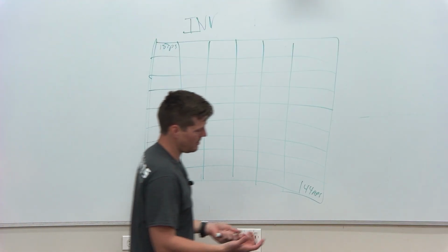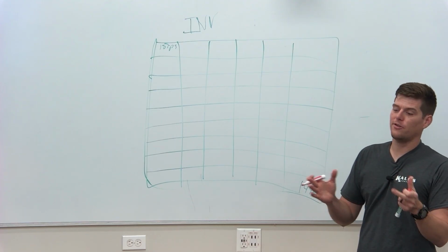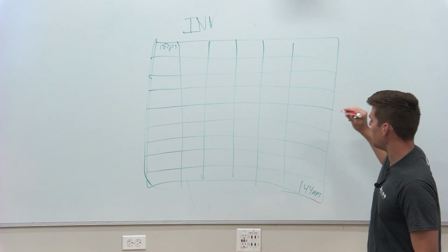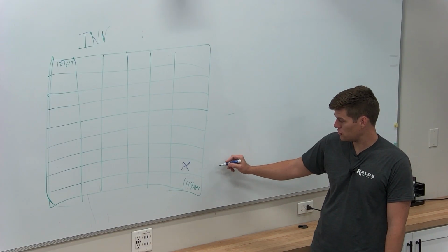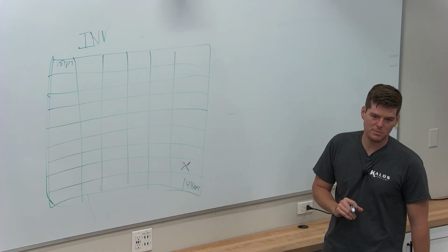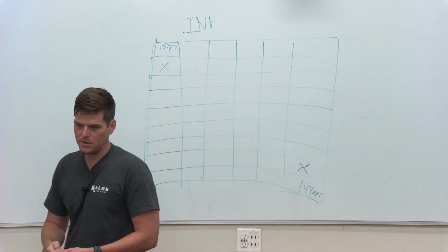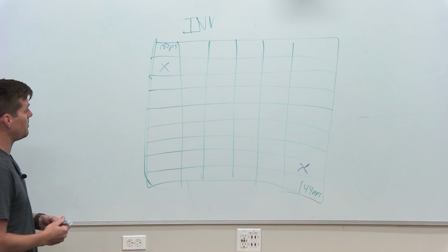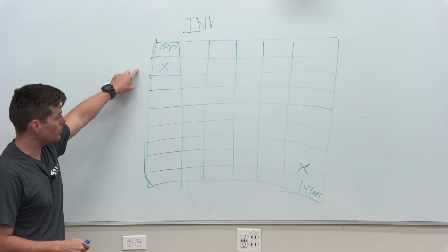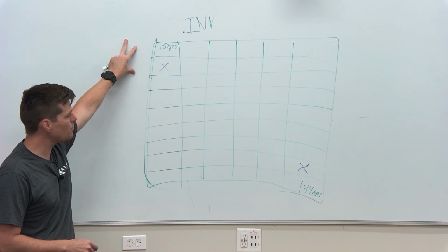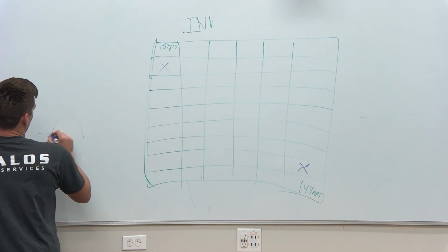This is like playing bingo. You asked me what the temperature differential between strainers is, right? So if I'm here on my compressor speed, then my temperature differential across strainers should be really low because the refrigerant is flowing at a high rate of speed. If I'm over here in this bingo square on compressor speeds, then my temperature differential across my strainers is going to be higher. Because again, if I'm over here, this is really slow. And if we know that this is a low, slow speed, then we know that the refrigerant is moving like a snail, right?